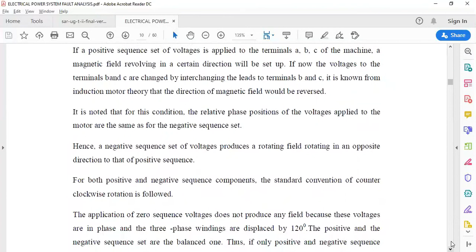It is noted that for this condition, the relative phase positions of the voltages applied to the motor are the same as for the negative sequence set. Hence, a negative sequence set of voltages produces a rotating field rotating in the opposite direction to that of the positive sequence. Means the directions of rotation of the positive sequence field and negative sequence field are opposite to each other. For both positive and negative sequence components, the standard convention of counterclockwise rotation is followed. So while checking the phase sequence, anti-clockwise rotation is followed conventionally. Almost in all reference books, you can find this particular notation.